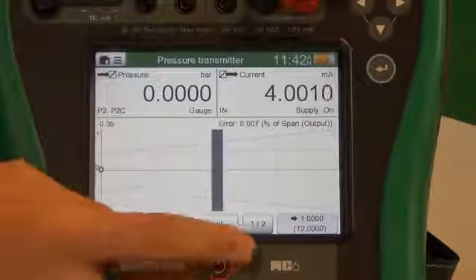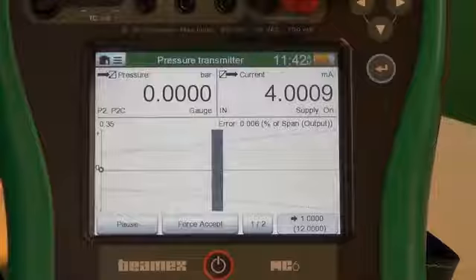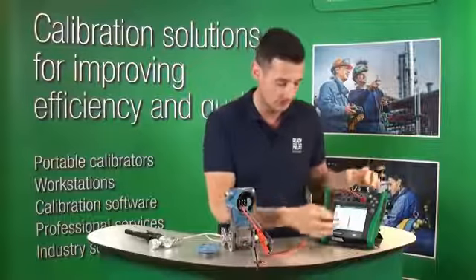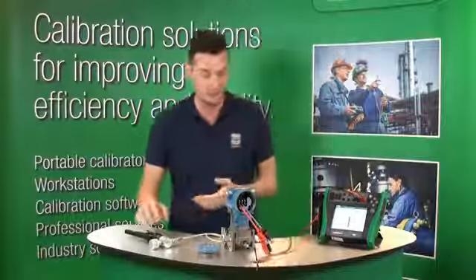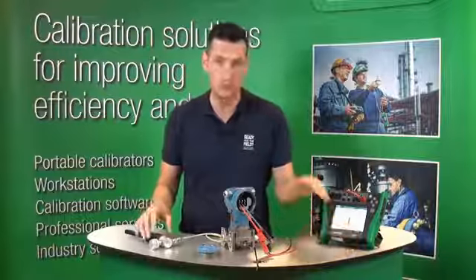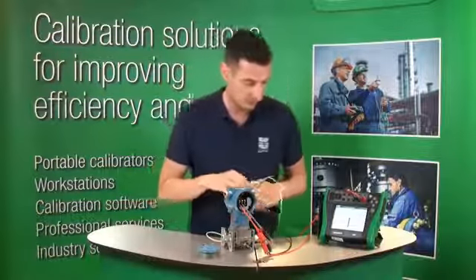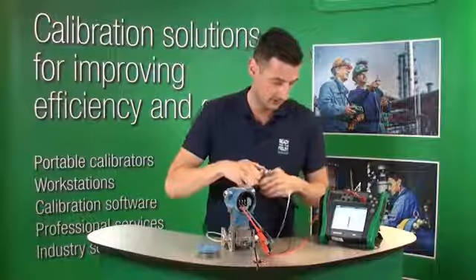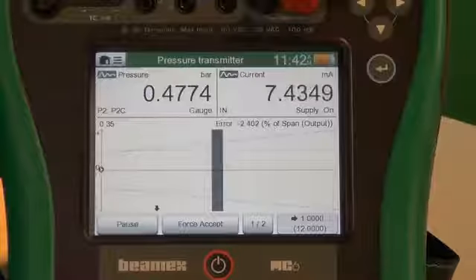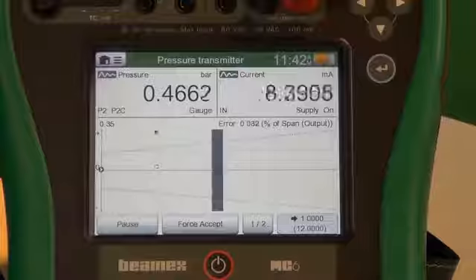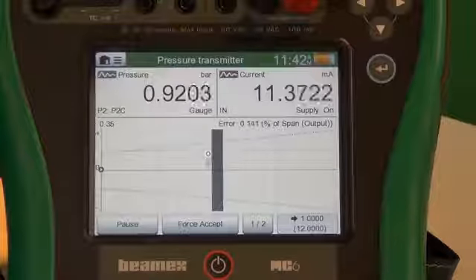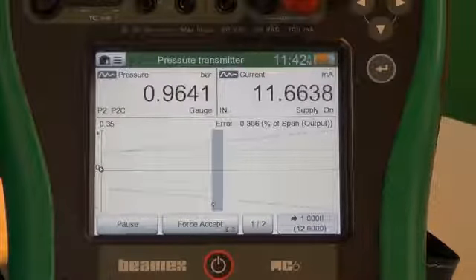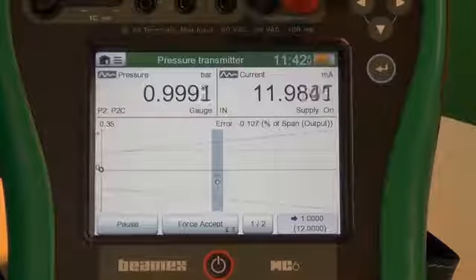The MC6 moves back to the first instrument, but goes to the second set point, 1 bar and 12 milliamps. So all we have to do is close the vent on the pump and try to pump up the whole system to 1 bar. Let's do that now.